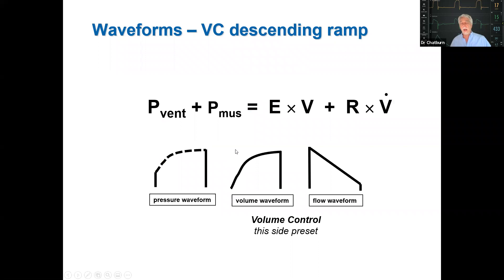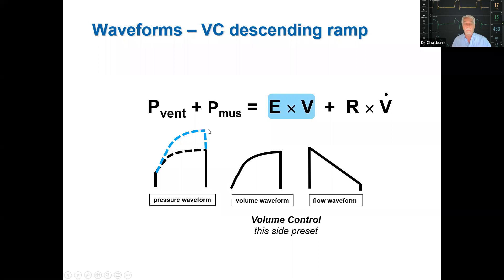Not everybody uses constant flow for volume control. At our institution, we tend to use a descending ramp flow, sometimes called decelerating flow. With a particular tidal volume and a descending ramp flow waveform, the pressure waveform reflects the equation of motion. If elastance increases, we see a larger end-inspiratory pressure. If the flow is set to zero at end-inspiration, the resistive term goes to zero and the end-inspiratory pressure equals the plateau pressure — so you don't even need an inspiratory hold, which some sick patients can't tolerate.